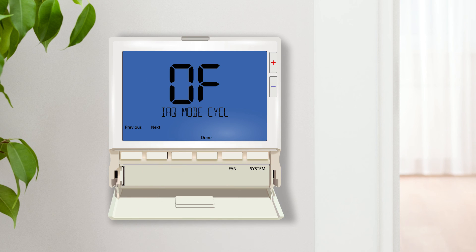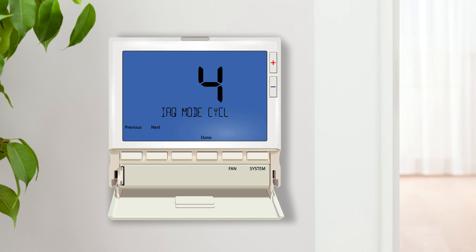IAQ mode cycle configures the fan to run up to 4 cycles per hour. Once selected, an additional text setting will follow, allowing you to choose the duration of time for each cycle. When this setting is on, IAQ fan will be available at the fan button on the home screen.